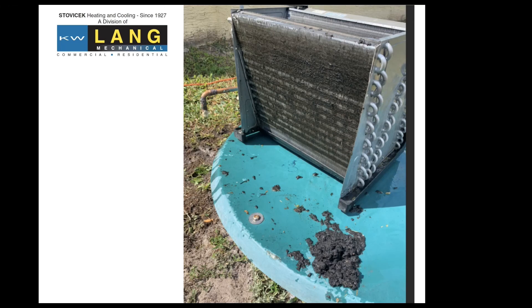This is one where we had to take the coil out completely because we couldn't clean it in the unit. Again, so preventable — just trying to stay ahead of the game. Everybody likes comfort and we find these on service calls. These are not found during the PM; these are just examples of waiting until it broke.